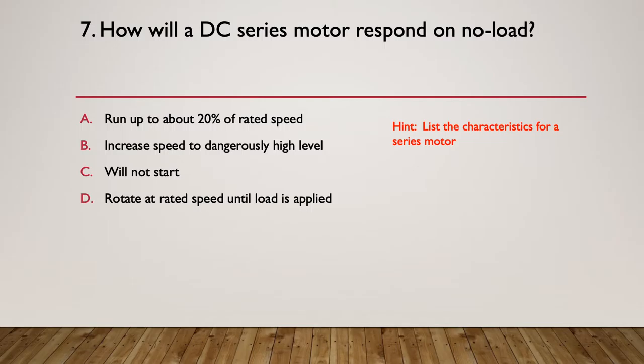A: Run up to about 20% of the rated speed. B: Increase speed to a dangerously high level. C: Will not start. D: Rotate at a rated speed until the load is applied. The answer is it's increased its speed to dangerously high levels. When we say dangerously high, it can rotate so fast that it will actually, the centrifugal force will quite often strip off the armature windings.